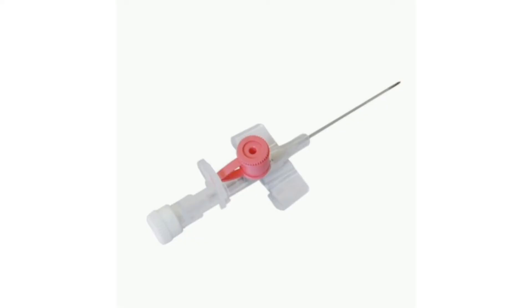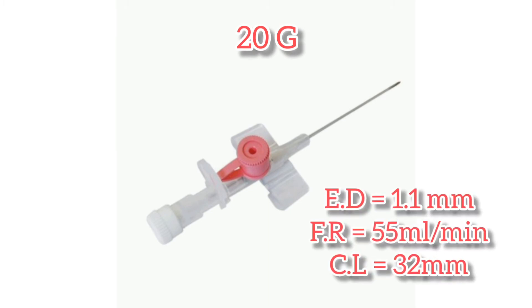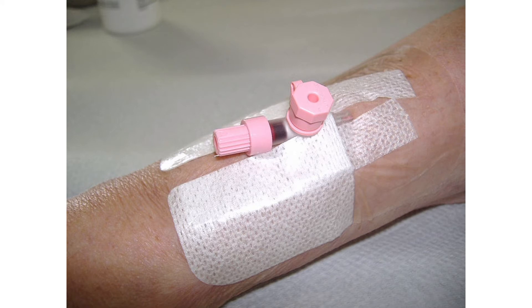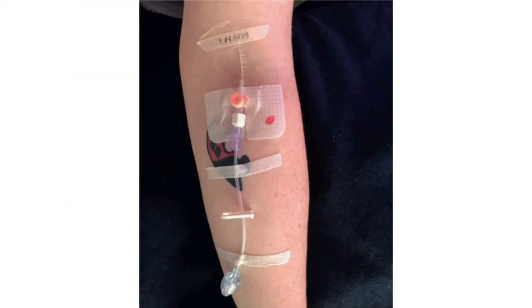The pink colored cannula has gauge 20. Its external diameter is 1.1 mm and the flow rate is 55 ml per minute. Catheter length is 32 mm. It is the ideal cannula for IV infusion and drug administration.